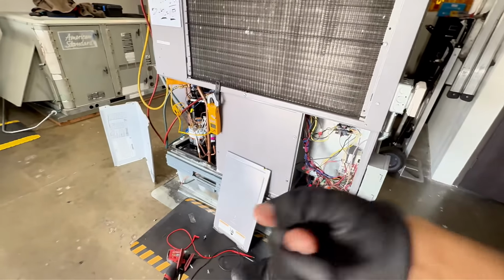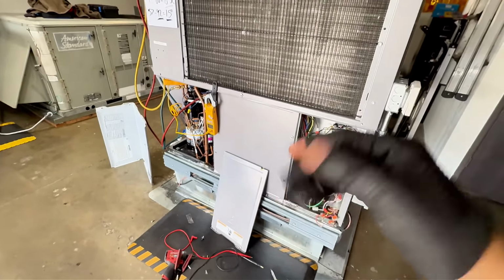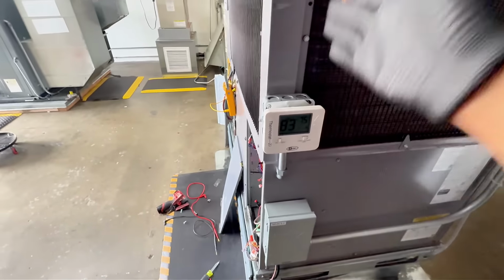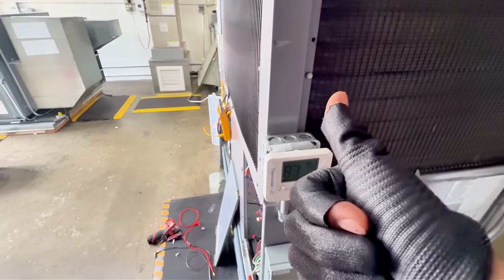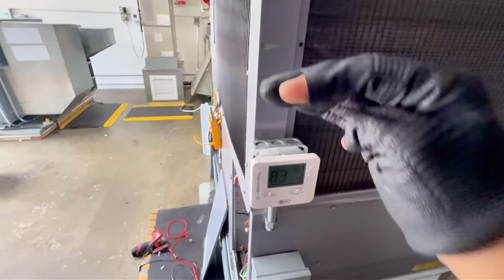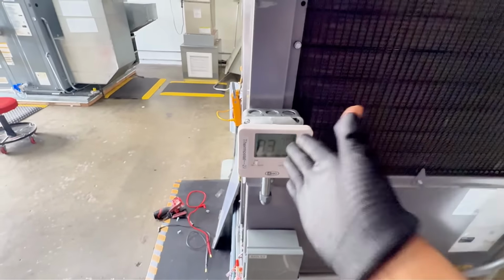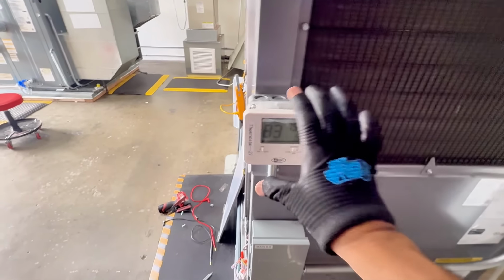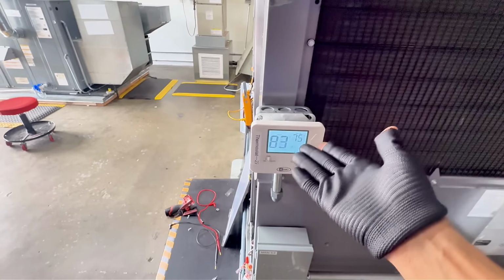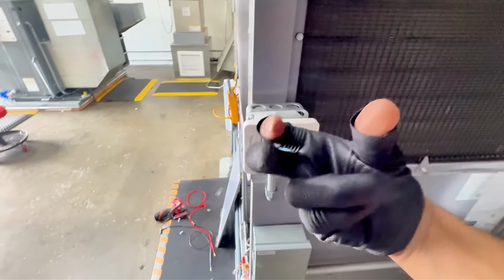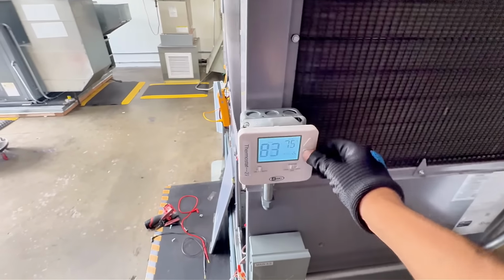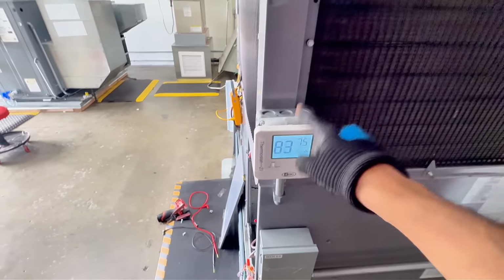Electrical. Find out the path that the 24 volts takes to make it to your contactor coil. All the systems, residential, commercial, there's a path that 24 volts takes to make it to your contactor coil. It starts right here with power. It comes right here. And my thermostat is blank, okay? And this is where I'm going to really break it down. If I have 24 volts in the back between R and C, and my thermostat head does not turn on, replace it. It's a bad thermostat head. Yes, make sure all the wires are in the right place. The pins in the back of the thermostat head, everything clicks. But if you have 24 volts, you plug it in, and it doesn't turn on, bad thermostat head.